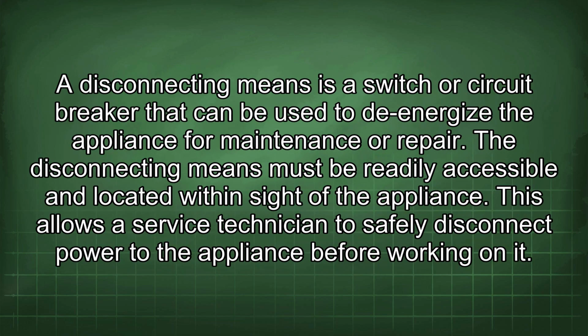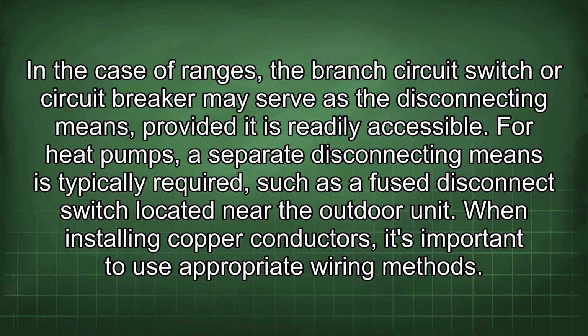A disconnecting means is a switch or circuit breaker that can be used to de-energize the appliance for maintenance or repair. The disconnecting means must be readily accessible and located within sight of the appliance. This allows the service technician to safely disconnect power to the appliance before working on it. In the case of ranges, the branch circuit switch or circuit breaker may serve as the disconnecting means, provided it is readily accessible. For heat pumps, a separate disconnecting means is typically required, such as a fused disconnect switch located near the outdoor unit.